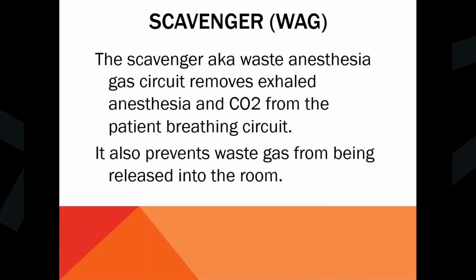If the scavenger is disconnected or not working properly, you'll get a plethora of issues that don't necessarily indicate that it's the scavenger or the WAG. You'll be looking at the patient breathing circuit, you'll be looking at the ventilator, you'll be looking at your gas circuit. And a lot of times it's because the scavenger's either been disconnected or something's happened to it where it's not properly pulling the gas out, because it's kind of a two-way thing.